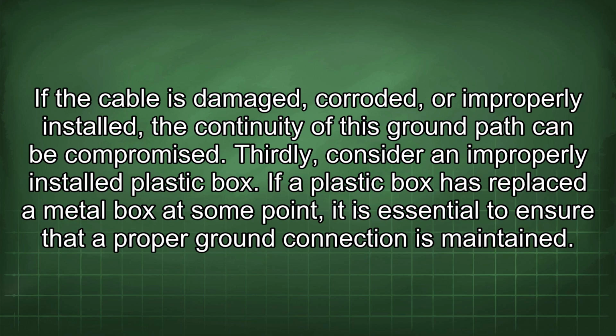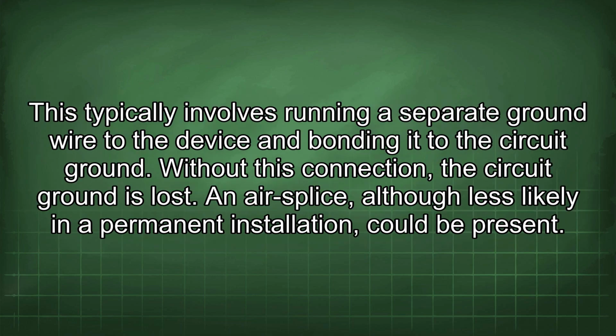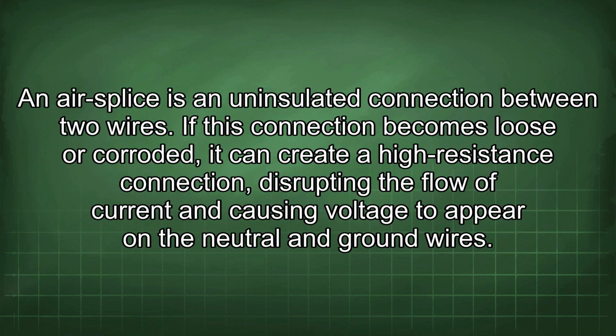Thirdly, consider an improperly installed plastic box. If a plastic box has replaced a metal box at some point, it is essential to ensure that a proper ground connection is maintained. This typically involves running a separate ground wire to the device and bonding it to the circuit ground. Without this connection, the circuit ground is lost. An air splice, although less likely in a permanent installation, could be present. An air splice is an uninsulated connection between two wires. If this connection becomes loose or corroded, it can create a high-resistance connection, disrupting the flow of current and causing voltage to appear on the neutral and ground wires.